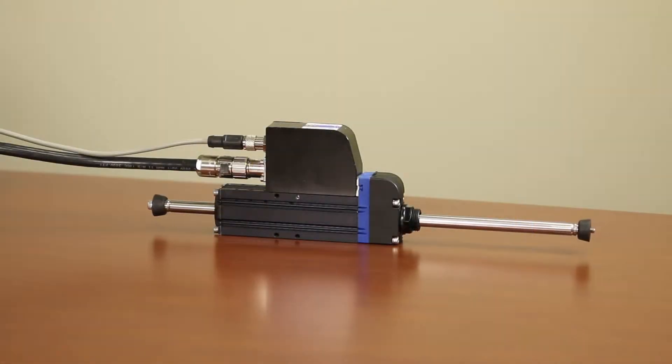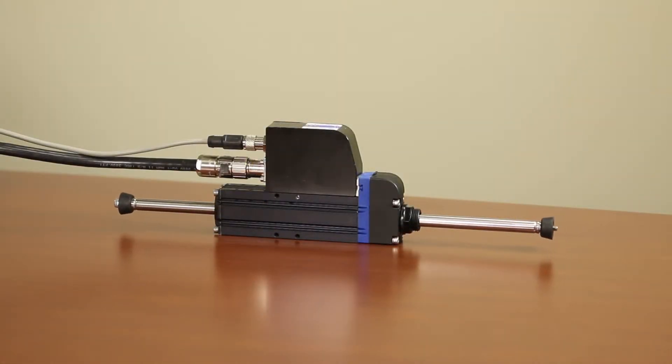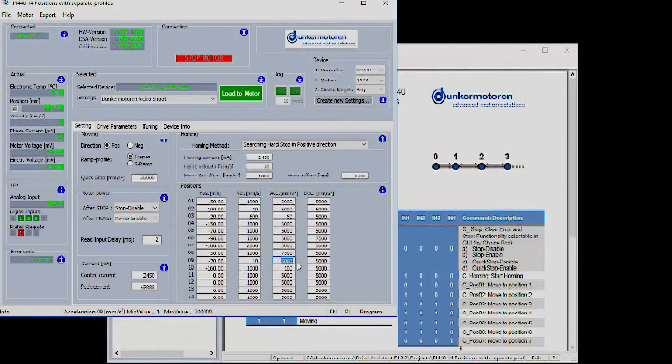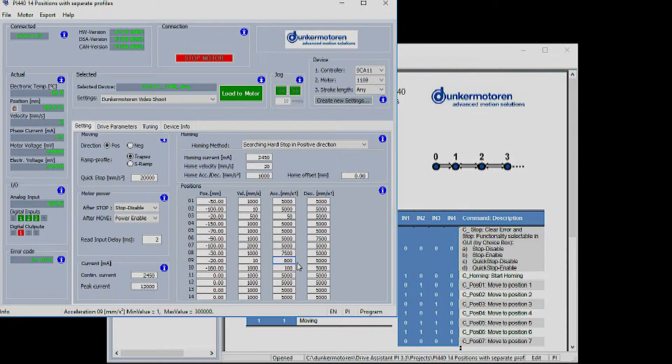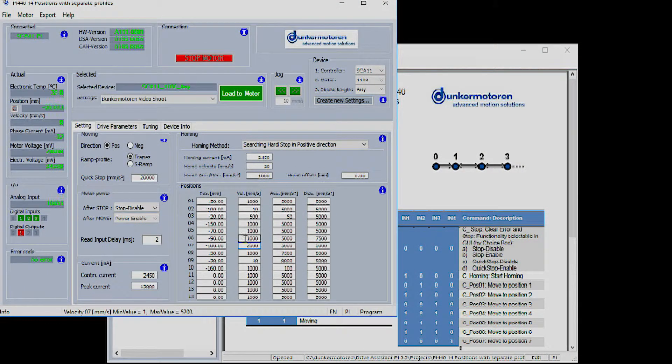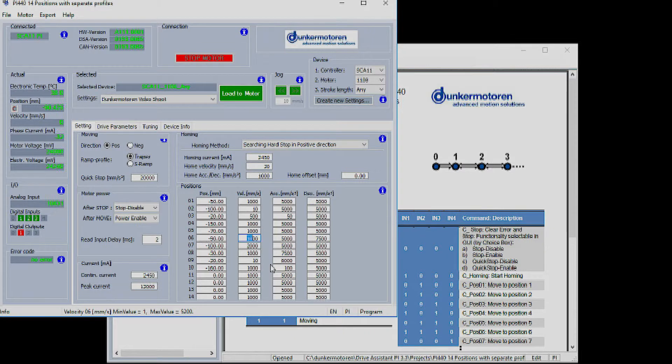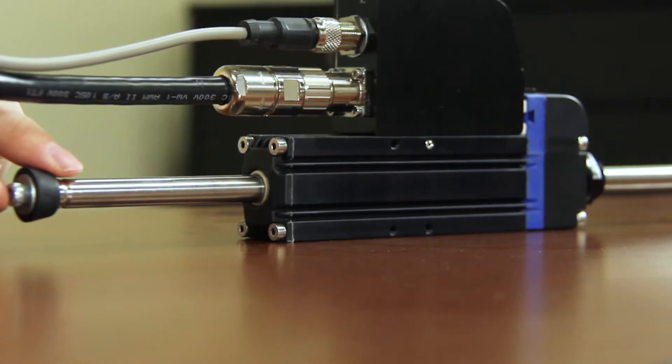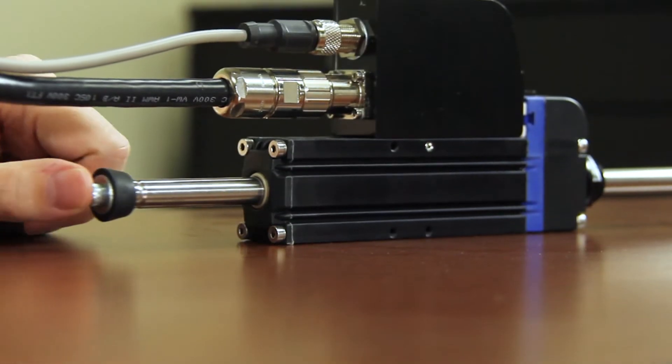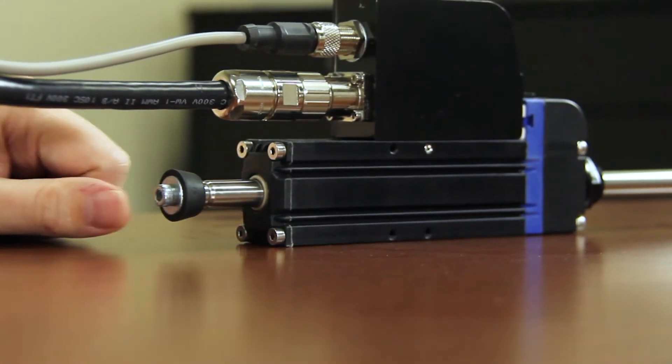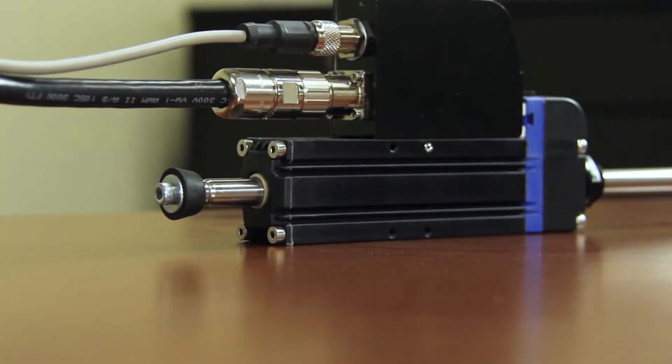The final component that needs to be set up are the positions. If the motor is free to move then you can verify the positions manually by setting the motor in its home position and moving the rod by hand. You can view the changing position counts on the actual data field in the software.